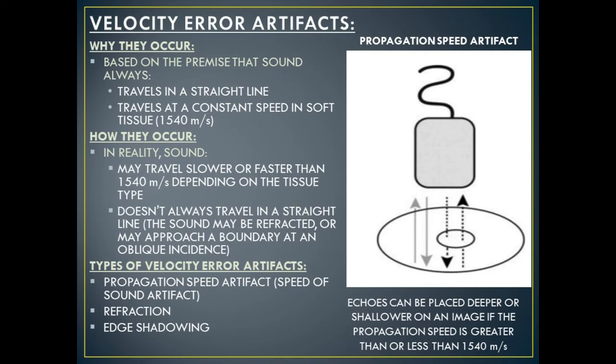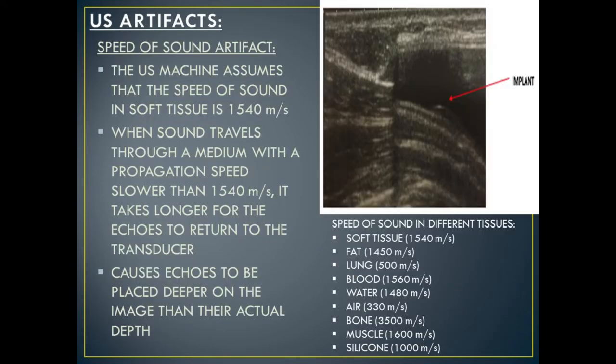Echoes can be placed deeper or shallower on an image if the propagation speed is greater or less than 1540 meters per second. Types of velocity error artifacts include propagation speed artifact, refraction, and edge shadowing. Speed of sound artifact, also known as propagation speed artifact, occurs when the ultrasound machine assumes that the speed of sound in soft tissue is always 1540 meters per second.